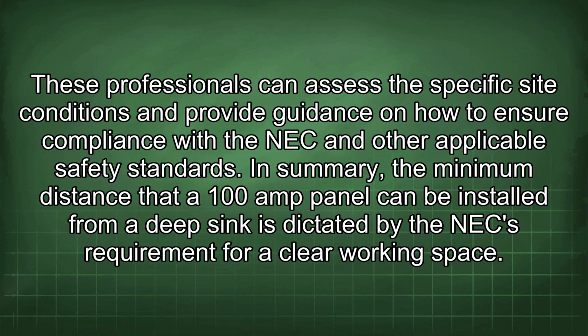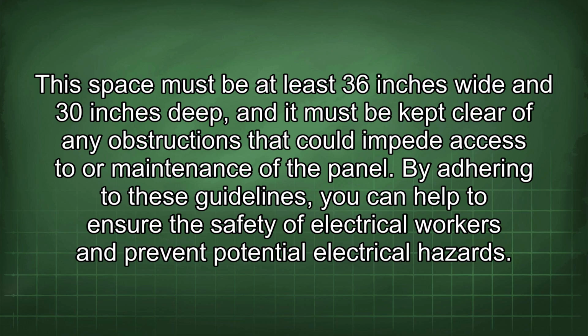other applicable safety standards. In summary, the minimum distance that a 100-amp panel can be installed from a deep sink is dictated by the NEC requirement for a clear working space. This space must be at least 36 inches wide and 30 inches deep, and it must be kept clear of any obstructions that could impede access to or maintenance of the panel. By adhering to these guidelines, you can help to ensure the safety of electrical workers and prevent potential electrical hazards.